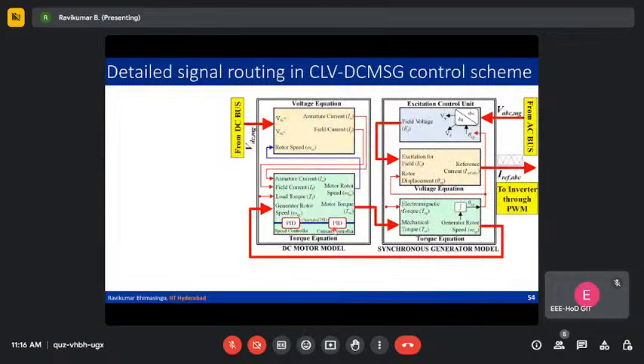This is the detailed signal routing of the closed loop virtual DC motor synchronous generator control. VABC is coming from the AC bus, and VDC MG is coming from the DC bus. Here we have a voltage equation, and armature current control, which is governed by two cascaded PIDs. There is an excitation control and torque equation, so whenever there are fluctuations in the DC side, the DC motor model provides the control mechanical torque.